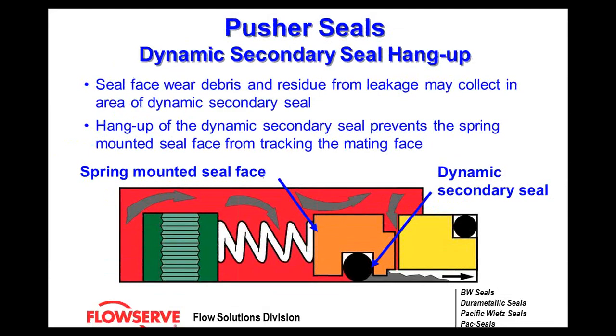Some pusher seal design limitations: because you have a dynamic secondary seal riding on a shaft, if you're in a system with contaminants or high heat, the leakage off the seal face can coke up. Those deposits build up underneath the seal and hang up the dynamic o-ring. These are really problematic in vertical applications with hot hydrocarbons — you can get coking on the inside that plugs up the dynamic seal quickly.